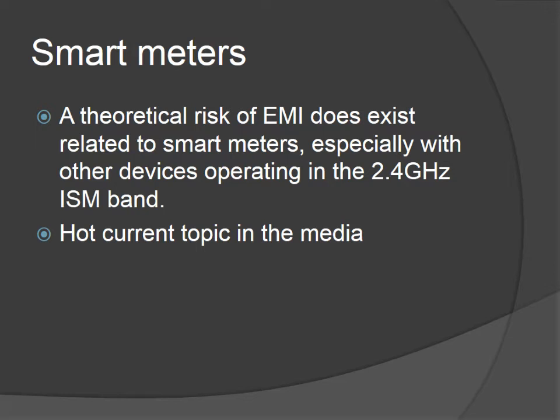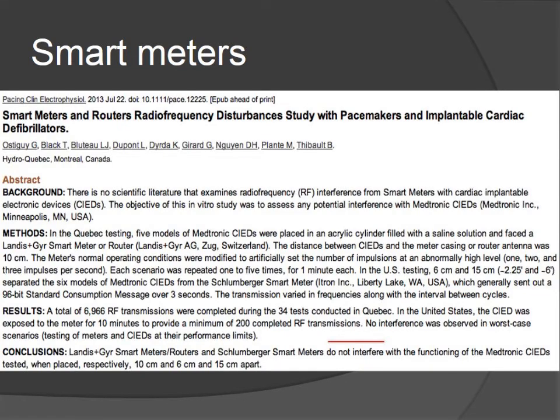However, in order to alleviate some of the fears, some work was done in collaboration with Hydro-Québec. A number of different smart meters were tested with a number of Medtronic devices, and we found there was no interference with device function when placed between 6 and 15 centimeters from the smart meter. There was transmission occurring at the time, with communication to the different devices. Active telemetry was not tested, but function and transmission of the smart meter was tested during this experiment.